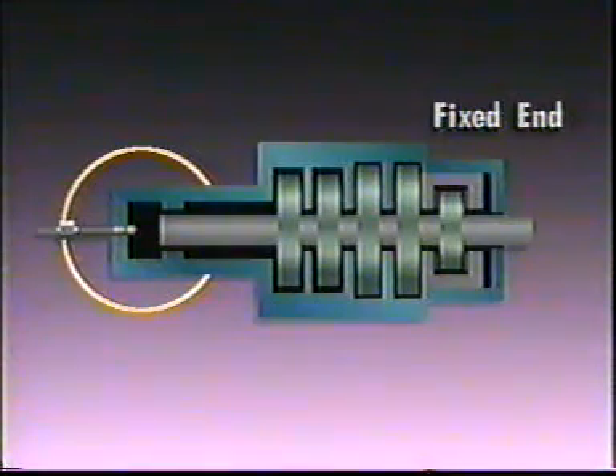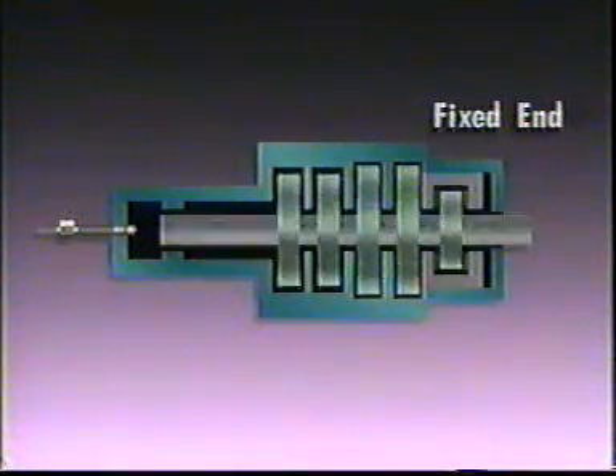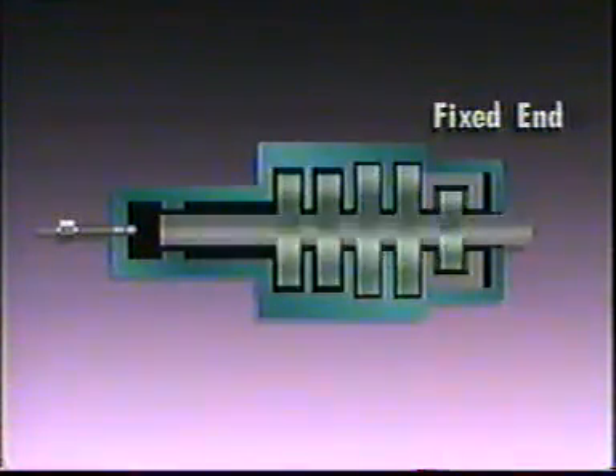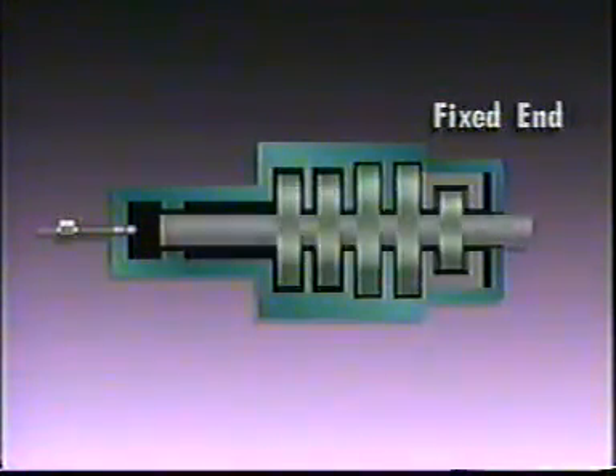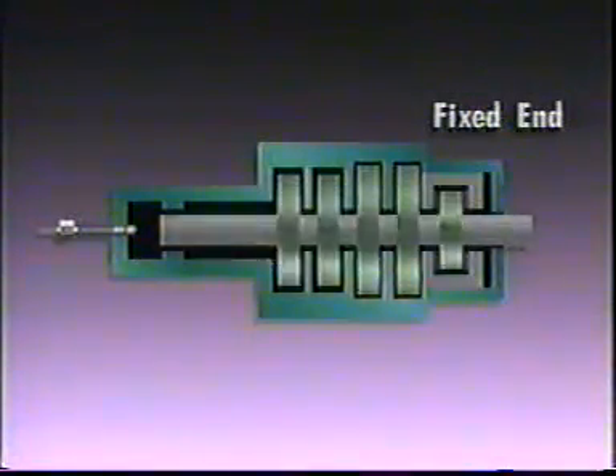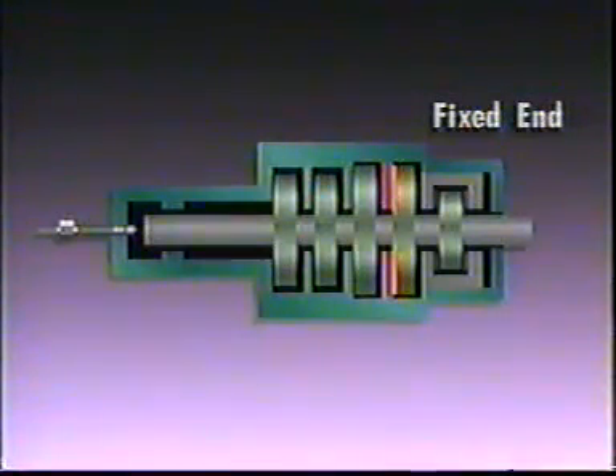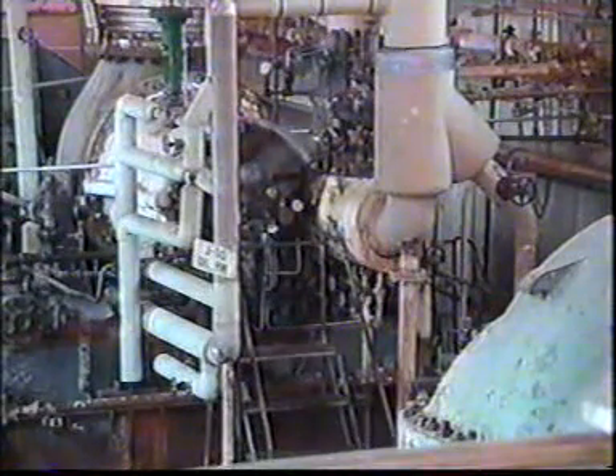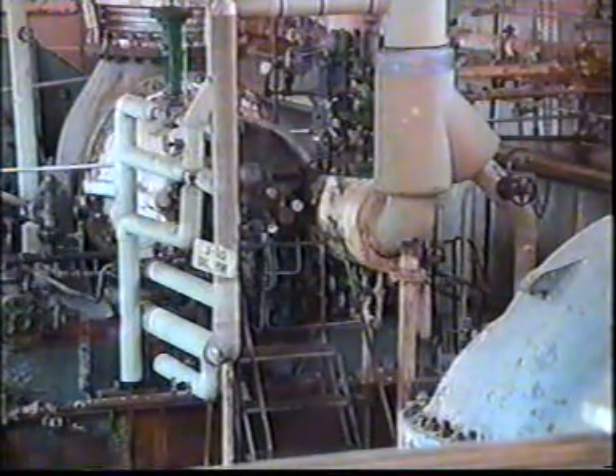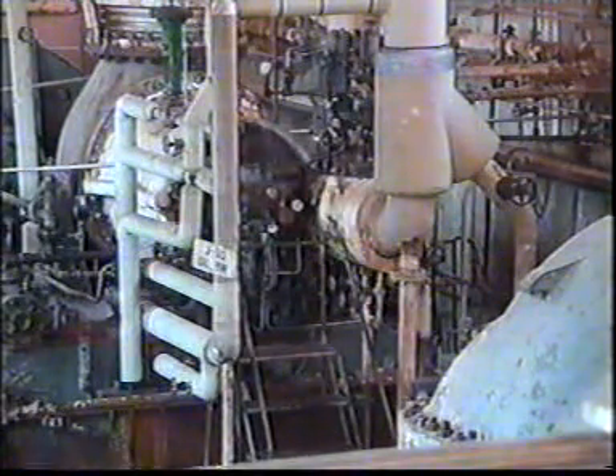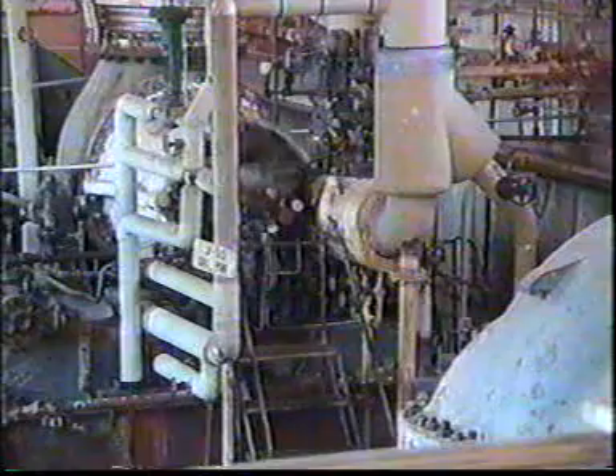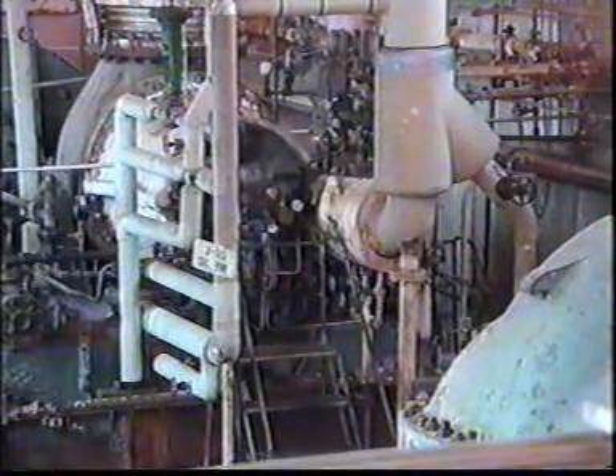The axial measurement shows differential expansion between the casing and the rotor, and is especially important during a steam turbine warm-up. The shaft expands faster than the casing when the steam is applied to the shaft. The shaft could expand in length as much as 2 inches. If differential expansion is excessive, the rotor could rub against the casing, damaging the turbine. Most large machines have one end rigidly fixed and the other end able to move for expansion and contraction. An expansion monitor will provide early indication of excessive movement.